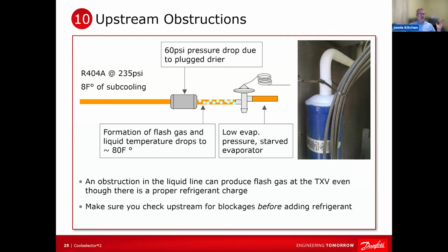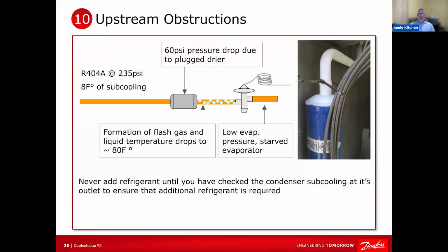Usually, it's not hard to find. You can walk by a solenoid valve and it's squealing like a banshee because it is either stuck part way or plugged or something. Your filter dryer looks like somebody sprayed the end of it with that fake Christmas snow, frost. You basically have 2 metering devices in a row, right? And so never add refrigerant until you verify all of these parts upstream and you check your subcooling at your condenser. Then you can add refrigerant charge.